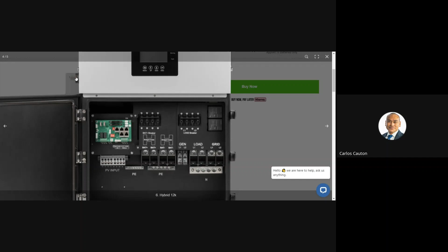Now you've got your ground for the solar, you've got your ground for your batteries. It has your communication cables, automatic transfer switch, and a rapid shutdown here on the left of the inverter. It's fully thought out, and it is a great inverter.